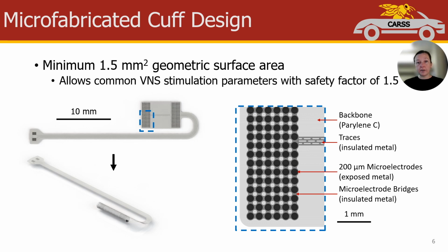Zooming in, the Parylene cable and cuff are microfabricated in a planar configuration, shown in the top left image, then thermoformed to form the self-sizing cuff in the bottom left image. The electrodes, which are on the inner surface of the cuff, have a minimum geometric surface area of 1.5 millimeters squared, which was set based on the properties of thin film platinum and common vagus nerve stimulation parameters, using a safety factor of 1.5. The image on the right shows a zoomed in portion of one electrode.